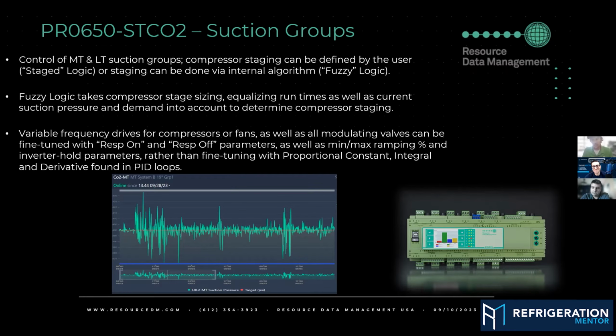It's not an instant deal. You're going to change this by 5 or 3, and then you're going to let it run and watch the graph. Sometimes it's instantaneous and you'll see it right away. Sometimes you got to wait. Come back the next day, check it out, see what it's doing, and then fine tune it from there.